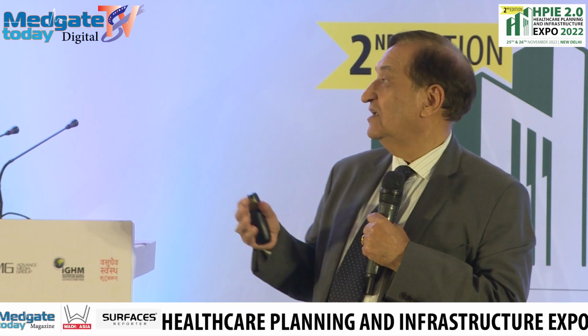Now people are saying these filters are very expensive. They are 4 times more expensive than a regular filter. Now how to make it usable: first, when you have a new project, you can use this filter and reduce the size of the AHU by 10 inches. By reducing the size of the AHU by 10 inches, you can have more space, and the pressure drop across these filters is 10 mm, whereas the pressure drop across a bag filter is 20 mm. So when you have a lesser pressure drop, you have a lesser energy requirement, and that can compensate the cost, and within 1 year the cost is recovered.